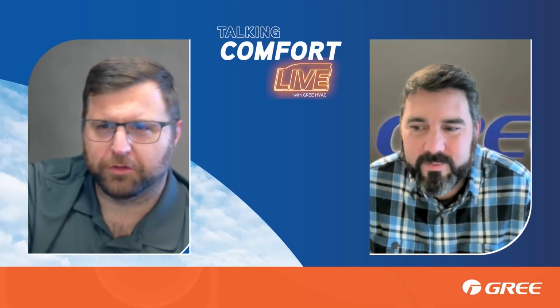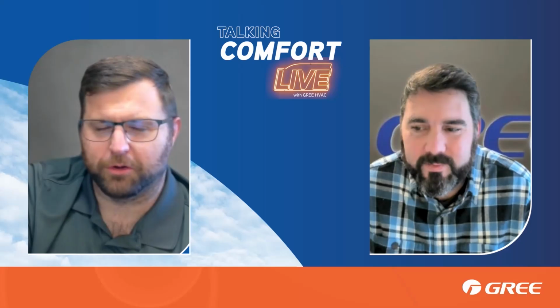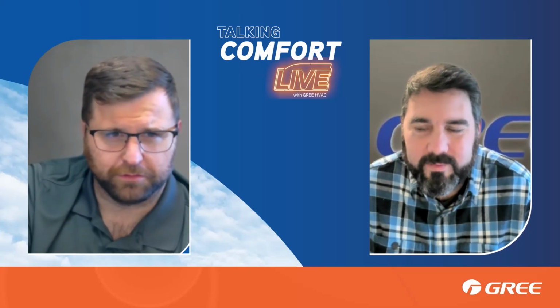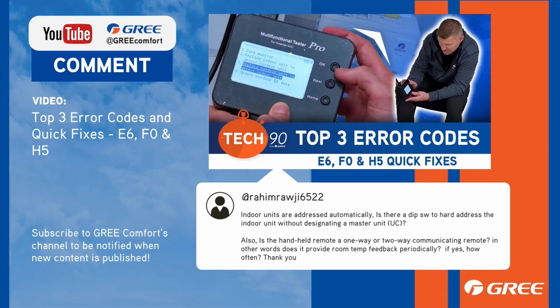As far as when we're talking about the address on the unit, are we making reference to the service tool giving you an address for the units, or because they're hardwired on the circuits? So it's not automatically addressed. Now on MultiPro and GMV systems, they are automatically addressed, and you do have to have a master unit for changeover. It doesn't allow you to change to opposite modes from the master unit, but you can change the master unit at any time. It's actually fairly simple to do.